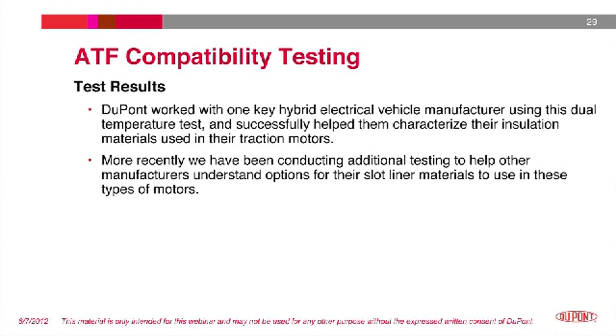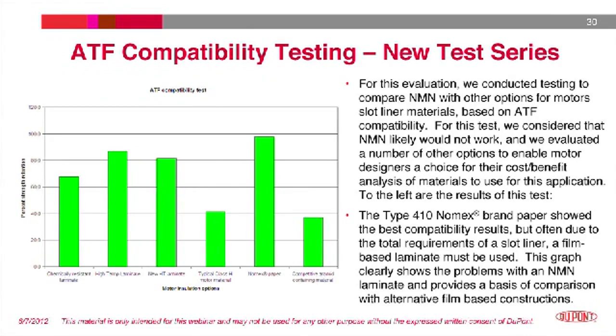More recently, we have been conducting additional testing to help other manufacturers understand options for their slot liner materials to use in these types of motors. In this more recent test, we evaluated a variety of motor materials for compatibility in an ATF fluid, as is shown here. The material most commonly used in Class H motors, an NMN laminate, will not work in combination with the ATF, as is shown in this figure.